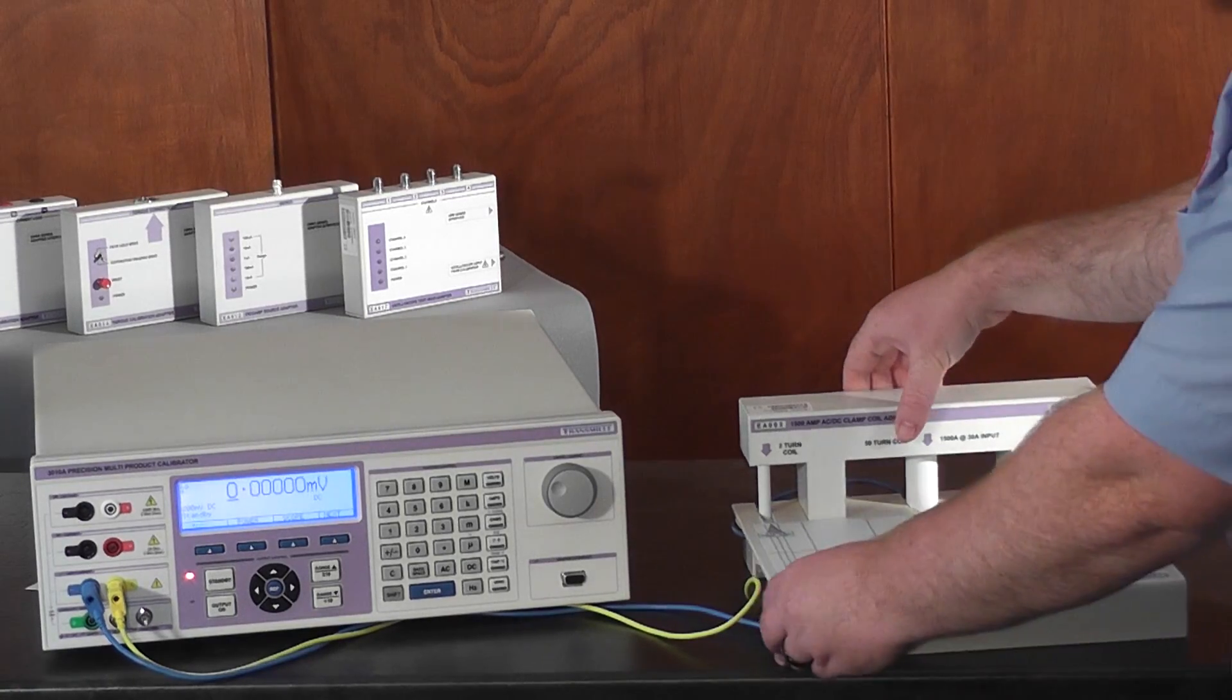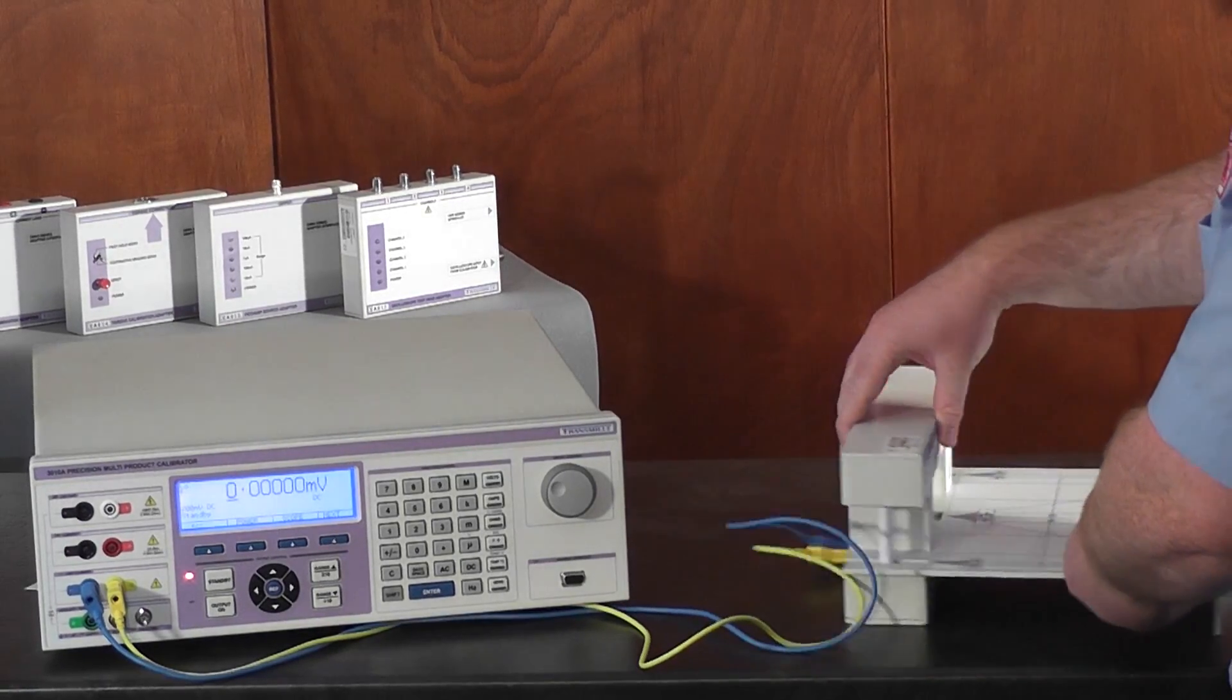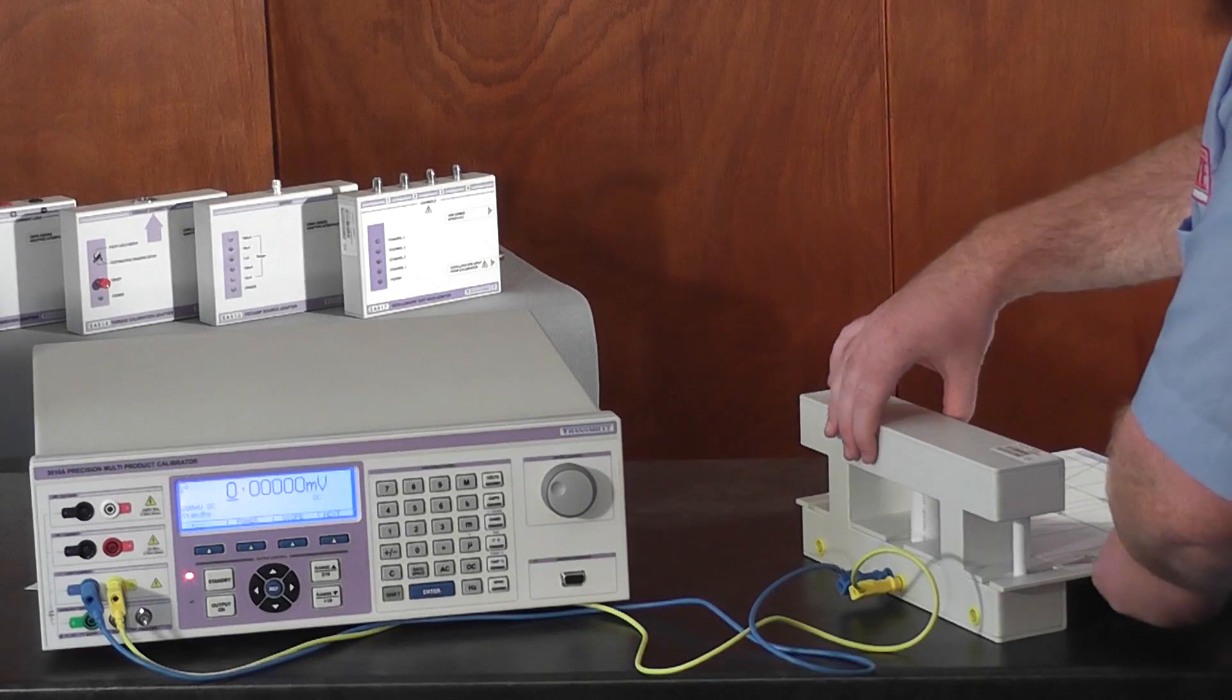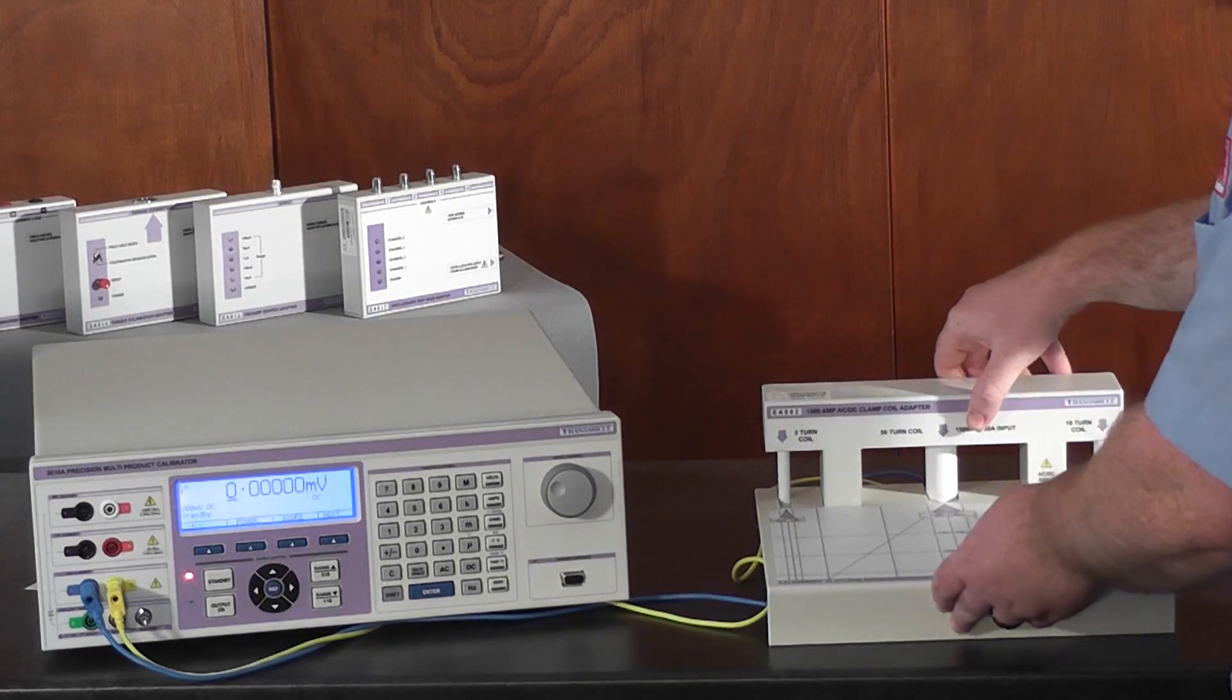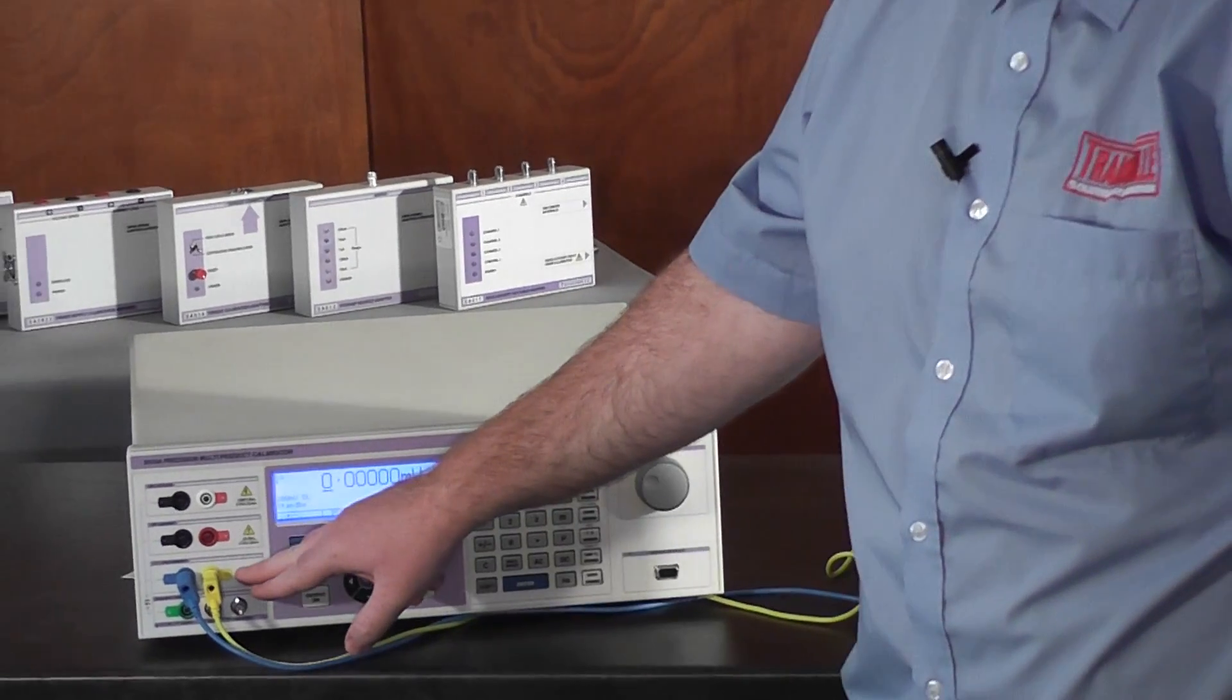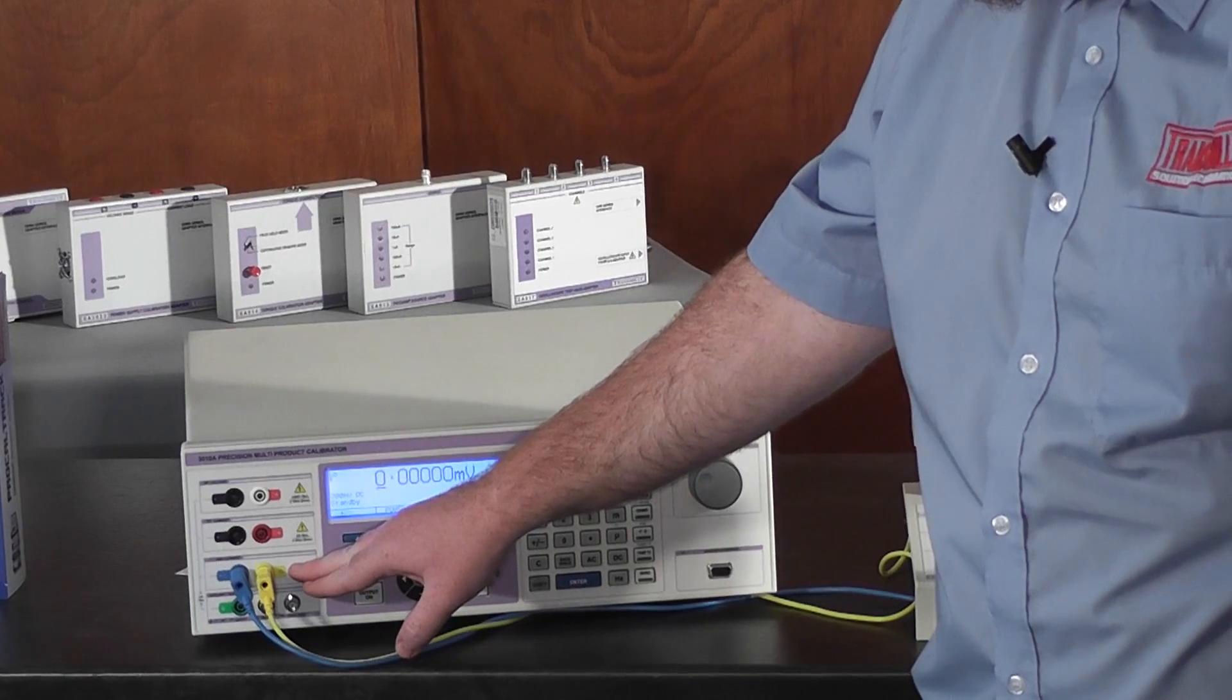Firstly, connect the calibrator to the correct terminals. Here I'm using the 50 turn input of the EA002 and connecting to the high current terminals of the 3010A.